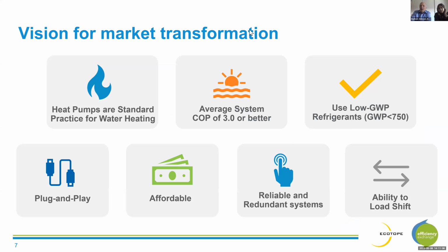And so Ecotope's vision of what we're doing here with water heating is really transforming the water heating industry so that heat pumps become standard practice instead of gas or electric resistance, that we're getting system COPs of 3 or better, that we're using low global warming potential refrigerants in those heat pumps, that they're delivered in a plug and play fashion so that there's very little specialized knowledge and experience needed on the part of the designers and installers, that they're affordable, that they're reliable, and that they have the ability to load shift. And we see this happening over the course of the next 5 to 10 years.